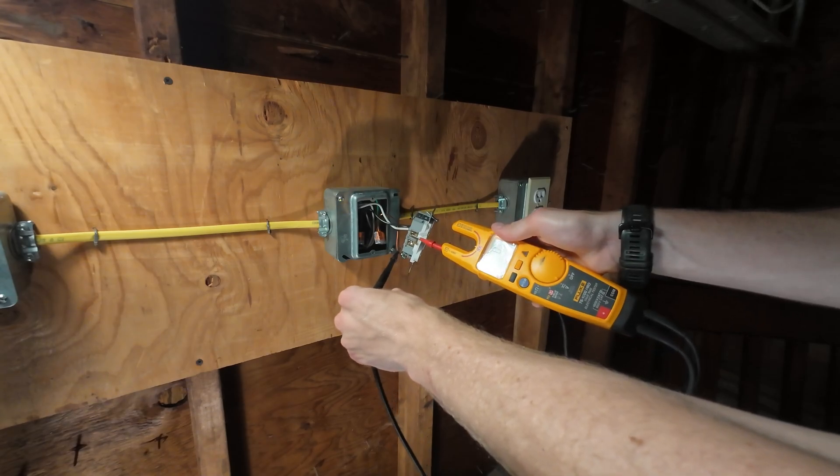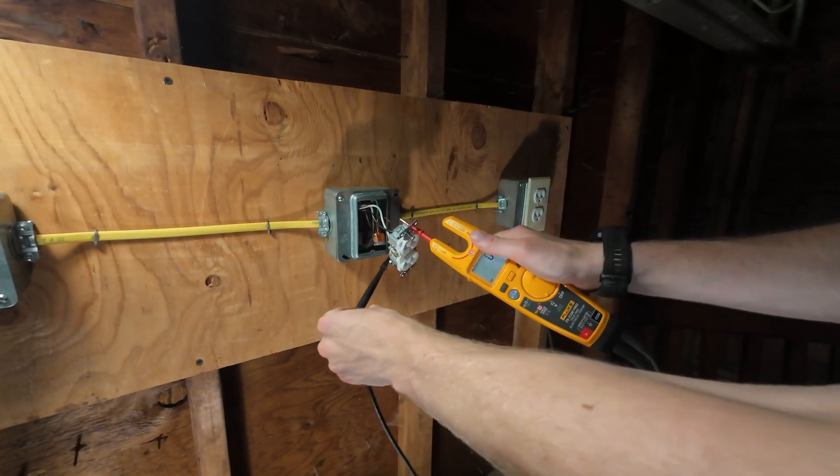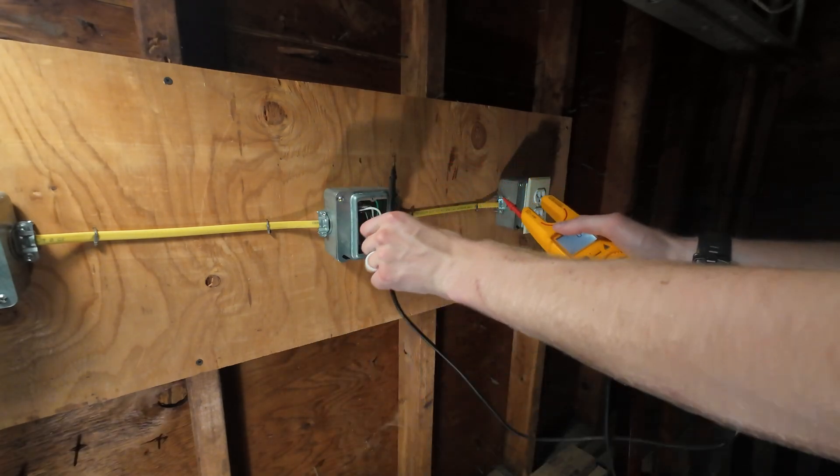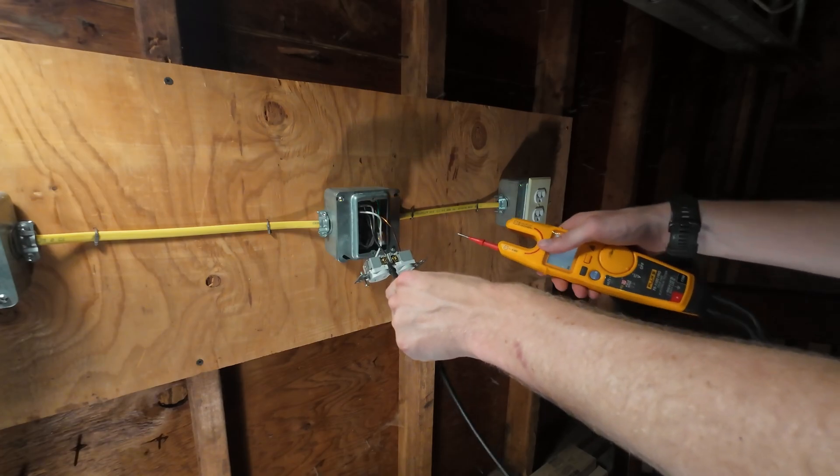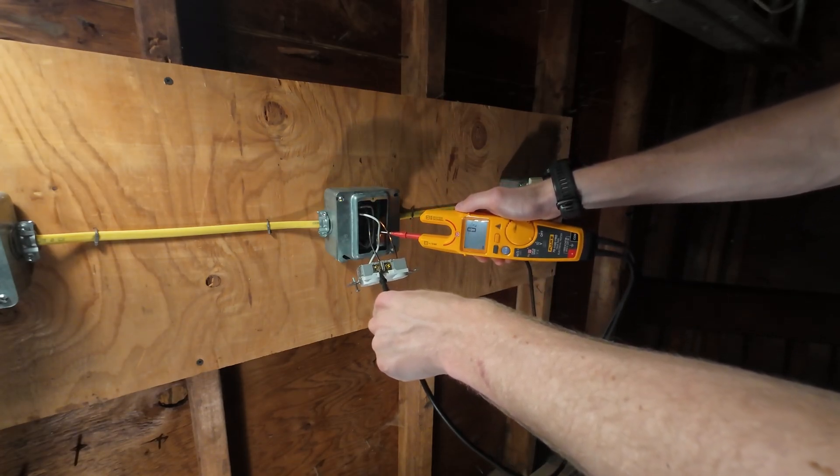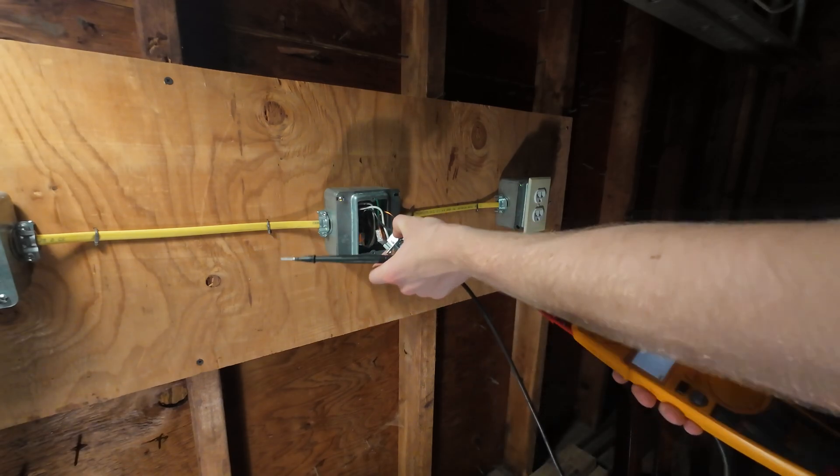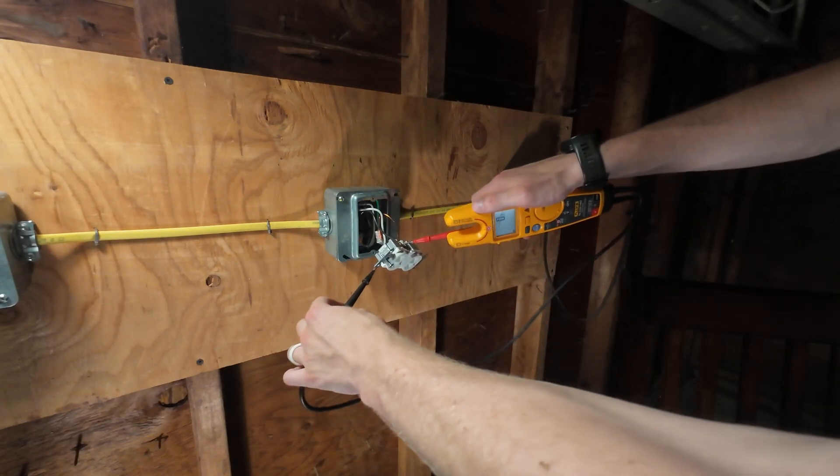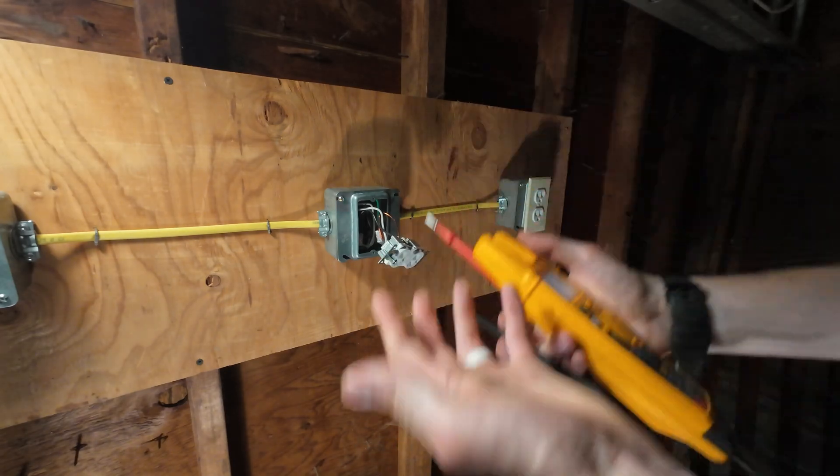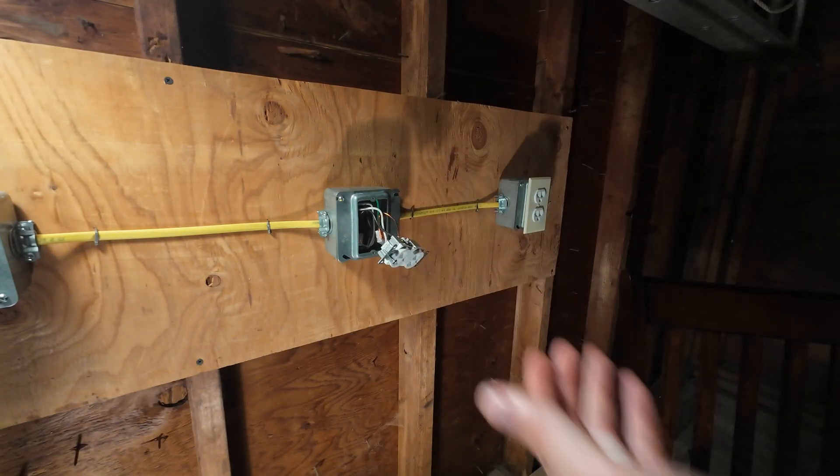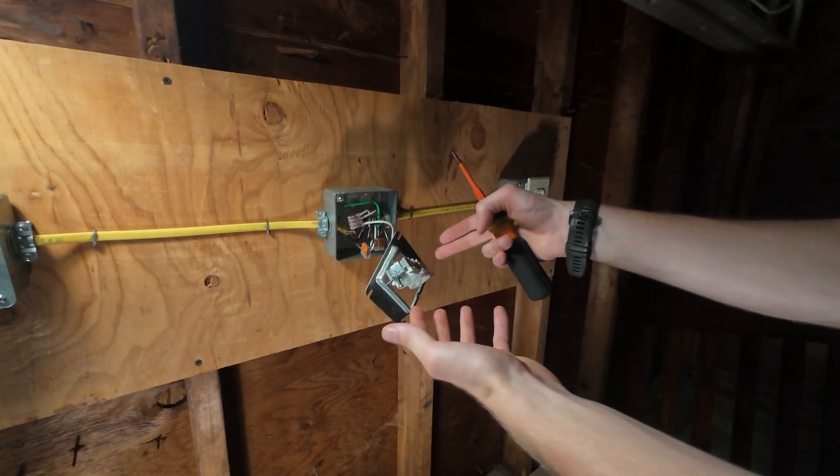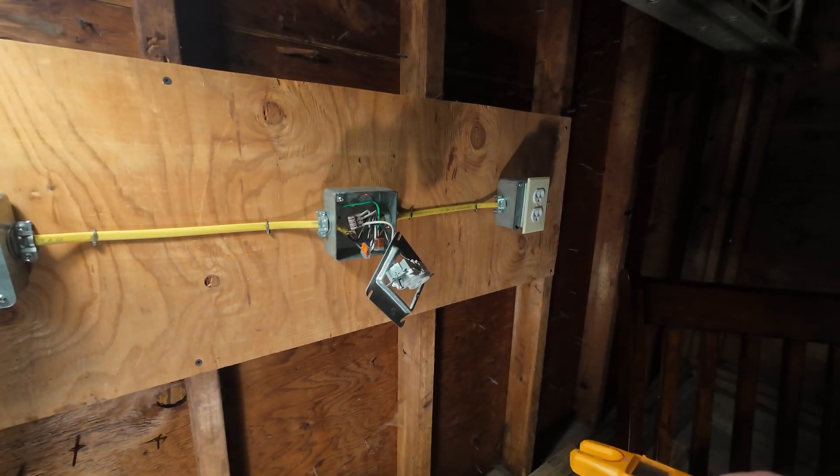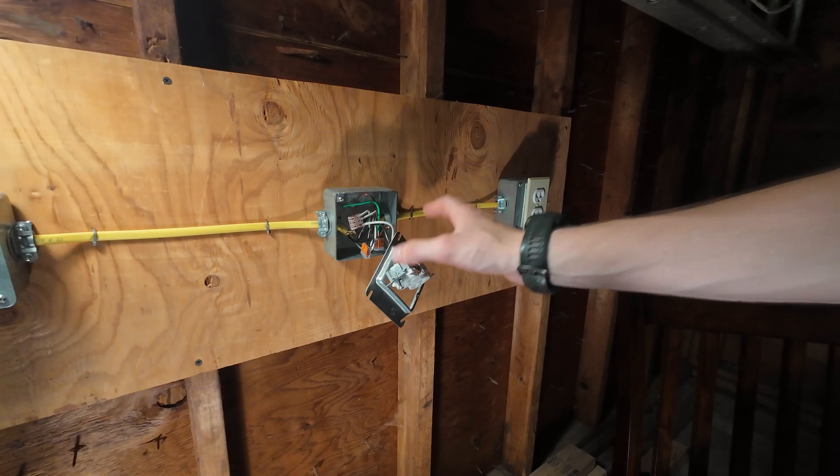So you remove the leads and I like to go from my white, which is my neutral, and I go to my ground. Let me turn the light on. You can see zero volts. Next I like to go from my hot, which is going to be my black, to my ground. I have zero volts. And lastly, I like to go from my hot to my neutral—zero volts. We know there's no voltage present, we know we can safely work on this.